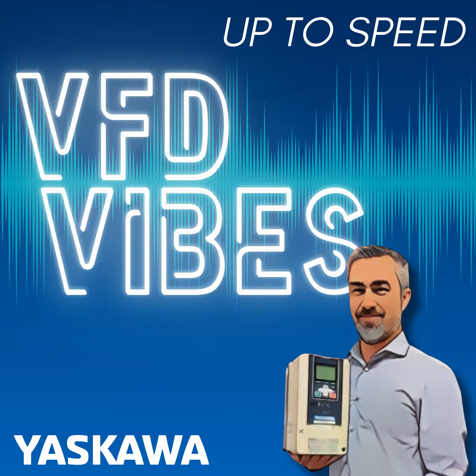So in most cases, these drive applications are very straightforward. You apply power to the front, you ground everything appropriately according to code, you bring your wires out to the motor, you hook the motor up, you run through your normal setup, the motor takes off and runs, and everything is fine. And I'll just say, if this conversation is confusing or scary to you, that's exactly why we have our applications team here. You can always call up when you're looking at your purchase, your spec, your facility, and we have people like Joe that can walk you through ahead of time. That's a key thing. We can be very helpful as application engineers when you're on the front end. When we're on the back end, and again, we deal a lot with retrofits.